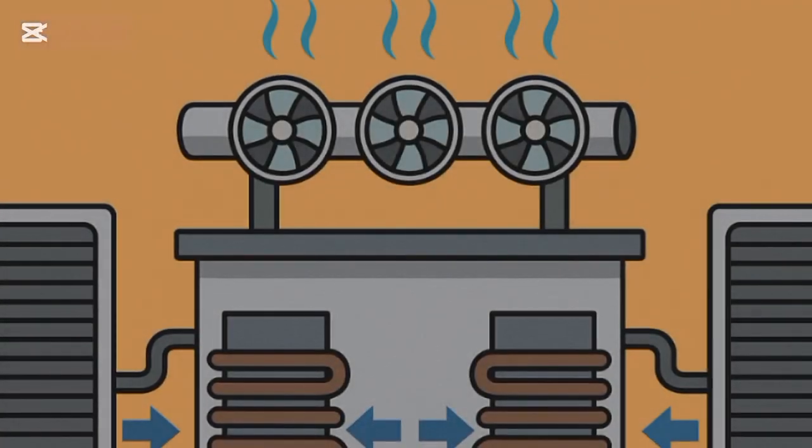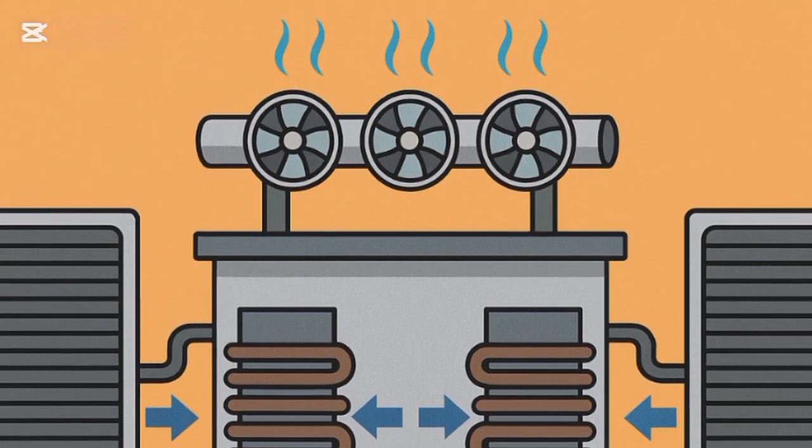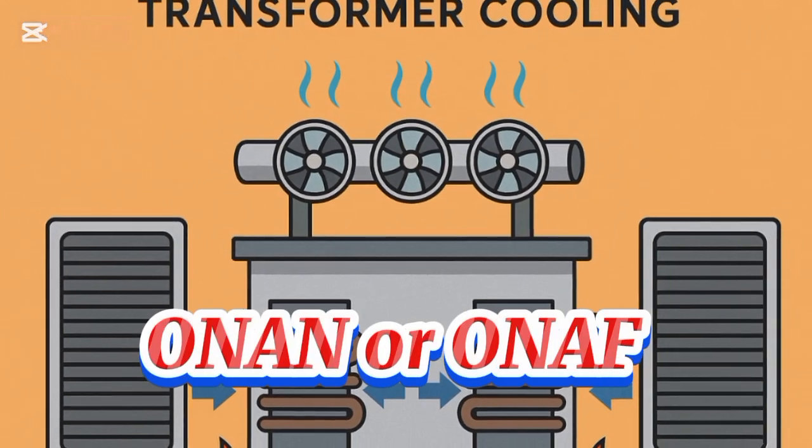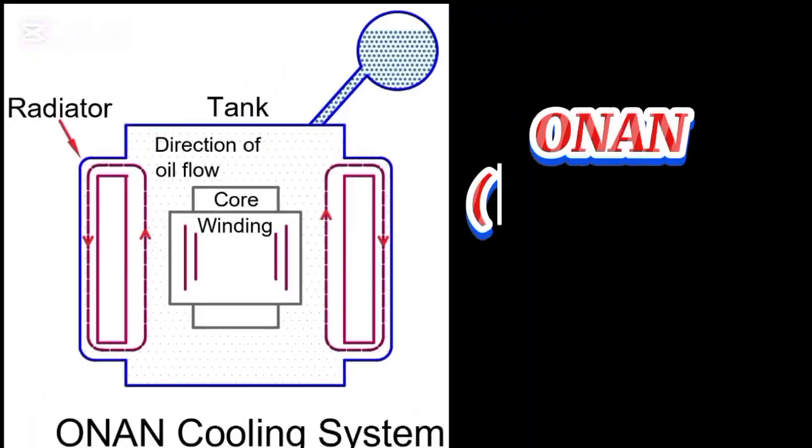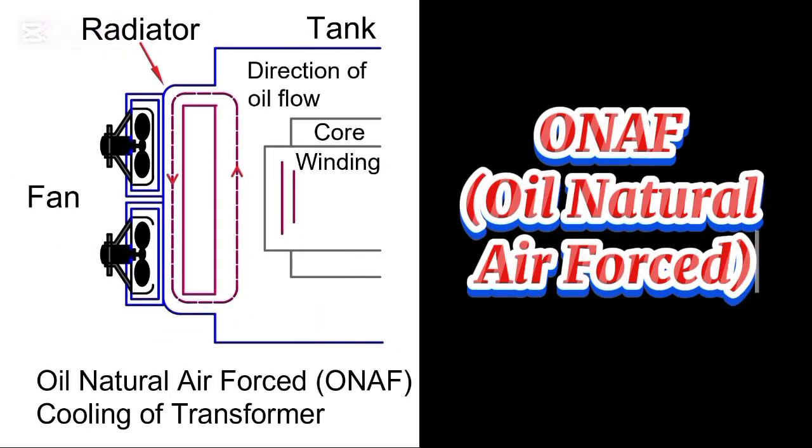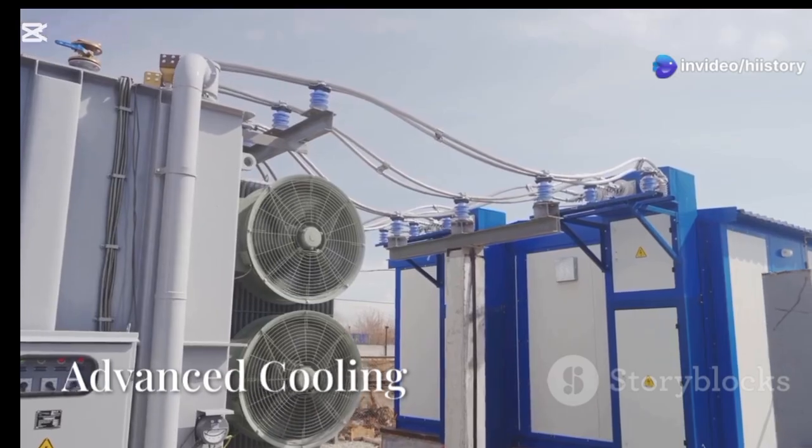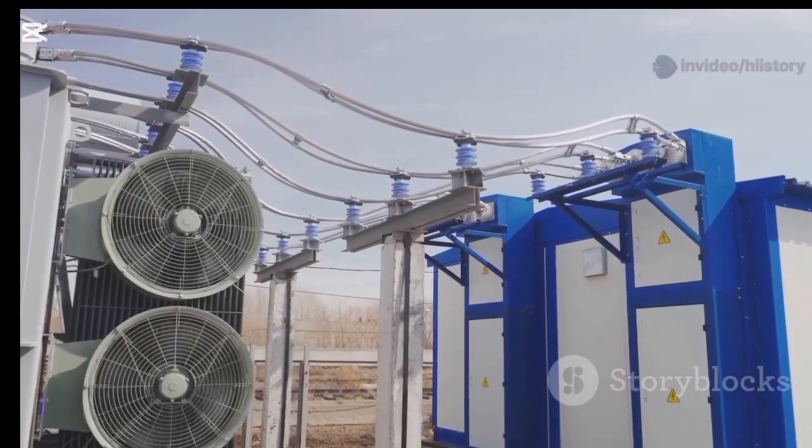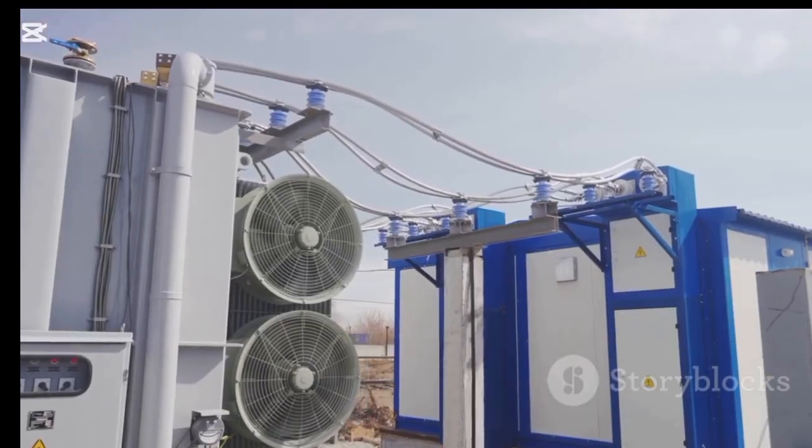Now, to manage all that heat, transformers employ air or oil cooling. You'll often see labels like ONAN or ONAF, which describe the cooling methods they use. ONAN means the transformer cools itself naturally using oil and air. ONAF adds fans to blow air and speed up cooling. Larger transformers may even use water to keep temperatures down.